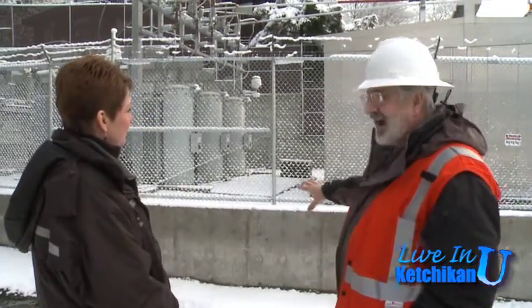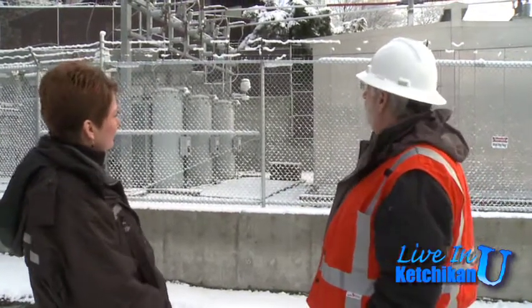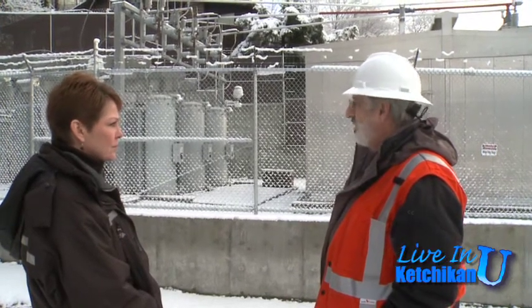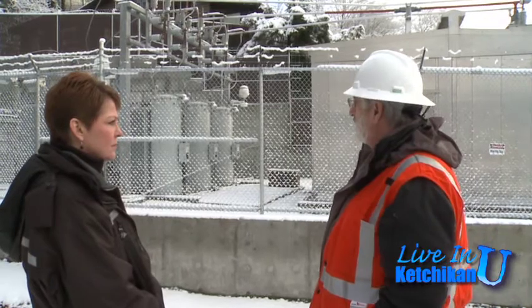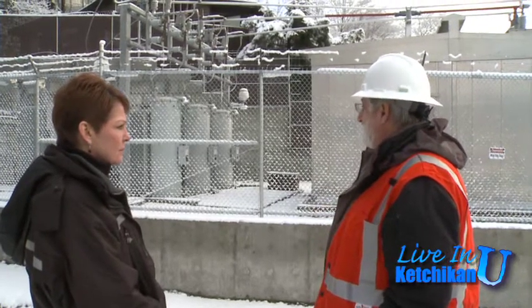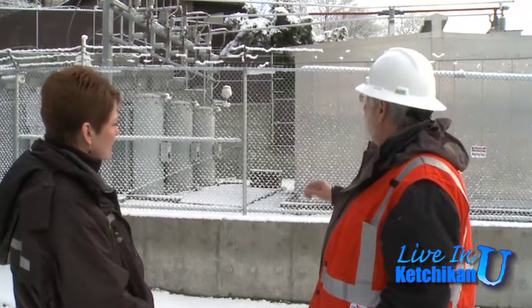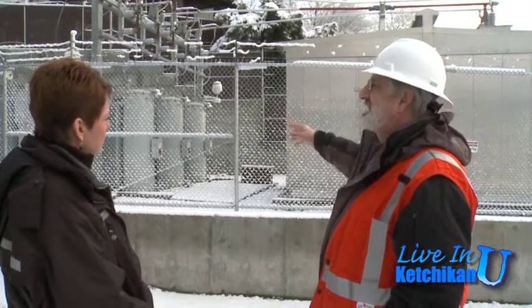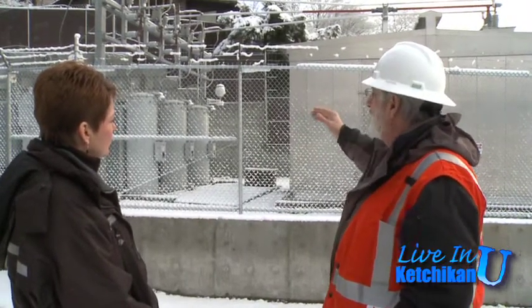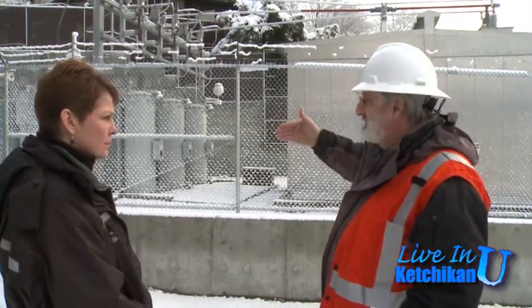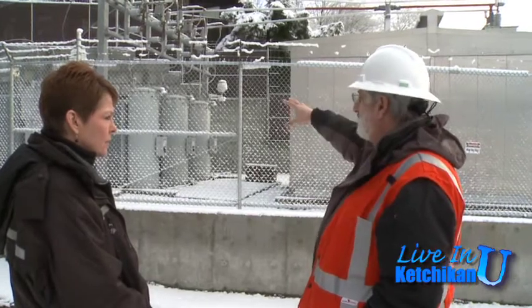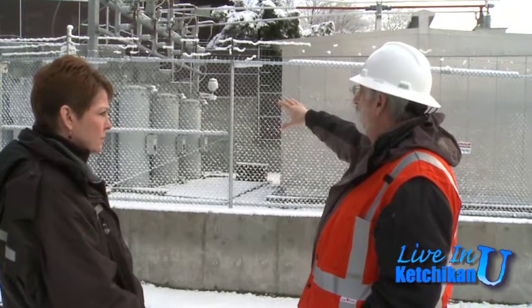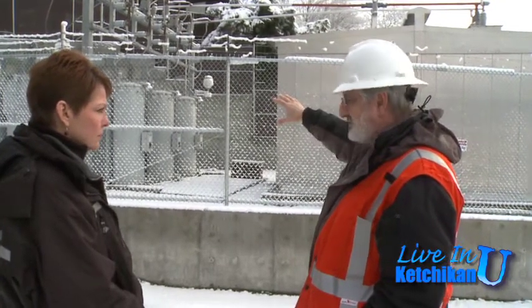Before, it was a 5 megawatt substation, and we were routinely in the winter months exceeding the 5 megawatts. So we were due to supersize this, and this is really supersized. This is a 12/16/20 megawatt station, and in those slashes there's additional cooling that comes on that gives you the next level. Ultimately, it's good for 20 megawatts, so 4 times the size of the original substation.